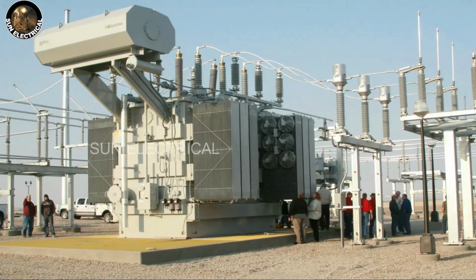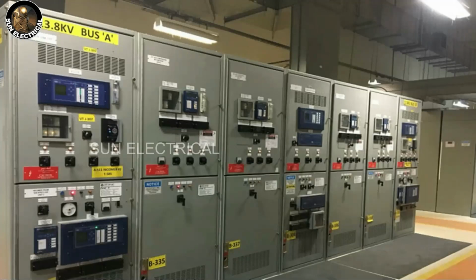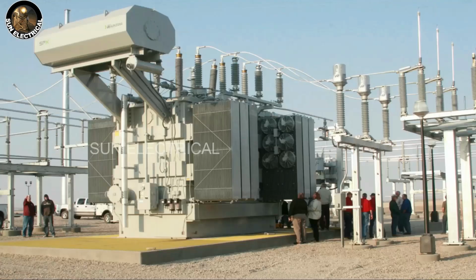In a substation or power station in any industry, DC supply is used for opening and closing the circuit breakers, to operate protective relays, to operate isolators, indicating lamps and alarms, PLCC, that means power line carrier communication, and emergency lighting in the control room, etc.